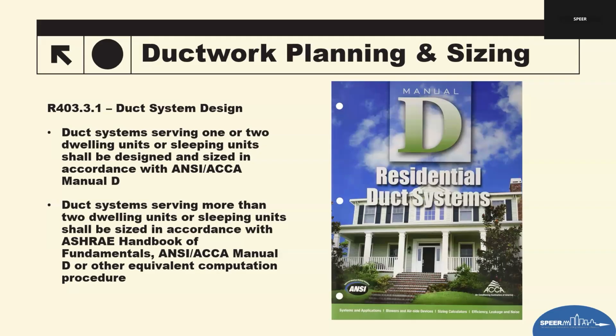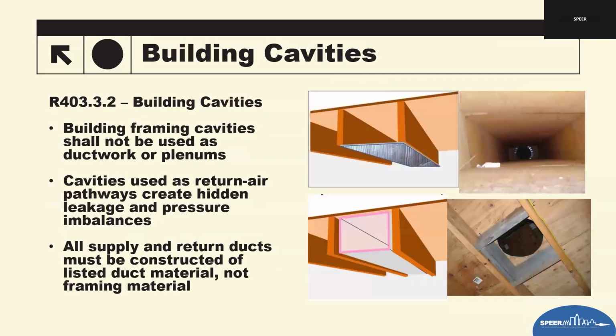So a properly designed duct system is one of the biggest factors in passing duct leakage testing and achieving comfort. When the duct system is wrong, everything downstream becomes harder: installation, balancing, meeting code testing thresholds, comfort of the home, humidity. All of this basically piggybacks on the fact that ductwork has not been designed properly or sized correctly. So that just turns out to say Manual D is the backbone of residential ductwork planning. Without it, everything becomes guesswork. And then the 2024 IECC is making sure that the systems are engineered, not improvised. I like that saying. So they're not guessing at it. They're not improvising while they're in the field. It's actually engineered, designed, and written and documented so that the field guys can follow that plan.